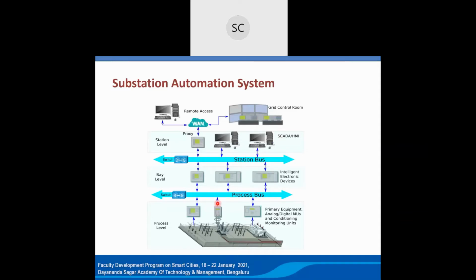For SCADA systems, there are two aspects. Protection is separate; we are not discussing protection aspects here, only SCADA, that is supervisory control and data acquisition systems. This covers all electrical parameters - voltage, current, frequency, power factor, power, reactive power - data fetching and control to various network elements, that is electrical network elements like breakers, switches, or transformer tap changers. That protection aspect we are not bringing into this distribution automation discussion; it is separate. But sometimes SCADA is included as a part, otherwise SCADA/DMS goes independently.